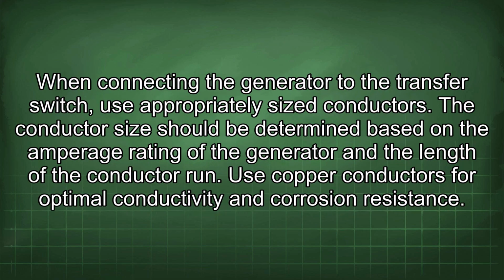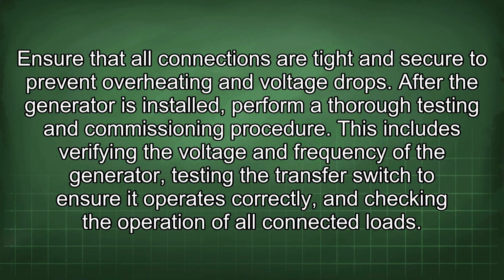When connecting the generator to the transfer switch, use appropriately sized conductors. The conductor size should be determined based on the amperage rating of the generator and the length of the conductor run. Use copper conductors for optimal conductivity and corrosion resistance. Ensure that all connections are tight and secure to prevent overheating and voltage drops.